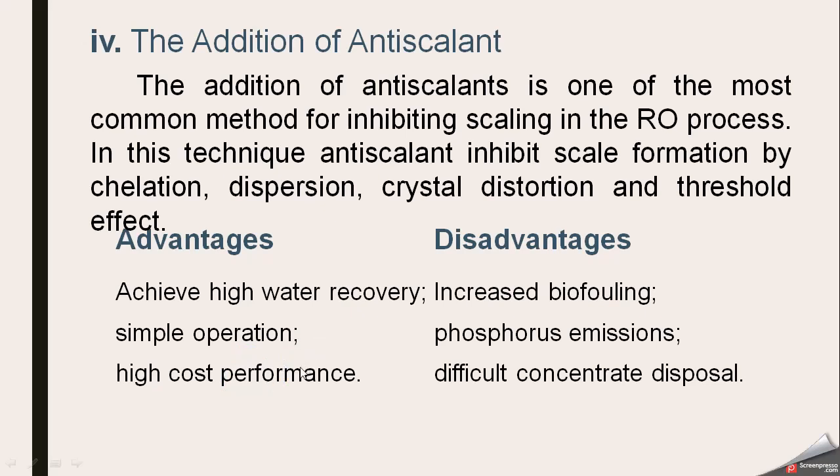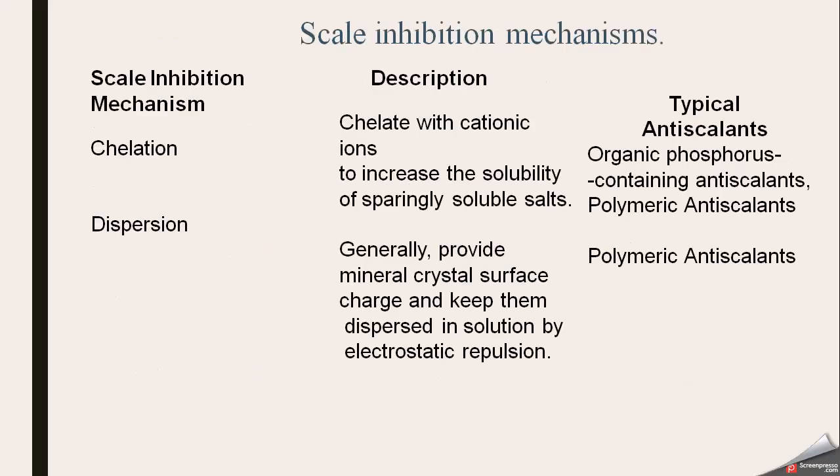However, the disadvantages are increased biofouling, because it focuses on the scaling, and phosphorus emission, because most of these are phosphonate and phosphate based compounds, so phosphorus in the discharge increases, and therefore concentrate disposal is very difficult. It becomes an environmental pollution problem to dispose of these highly concentrated phosphorus compounds in the discharge.